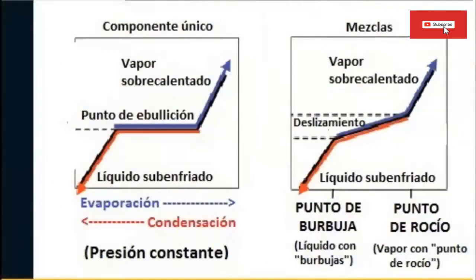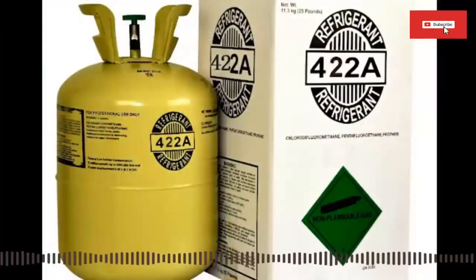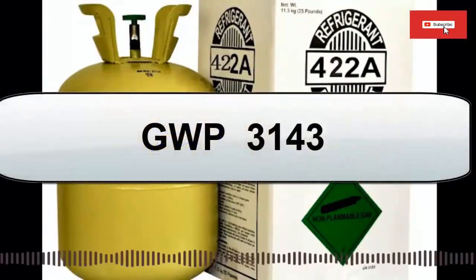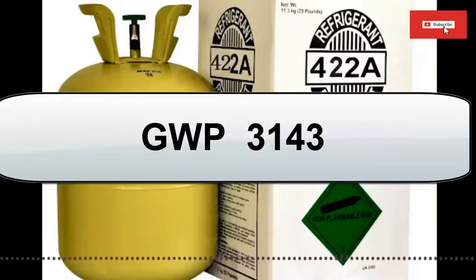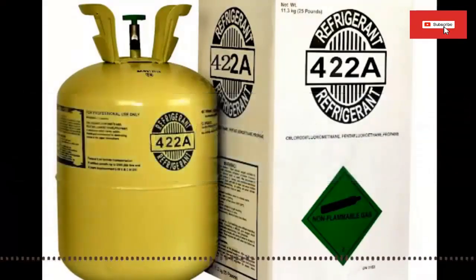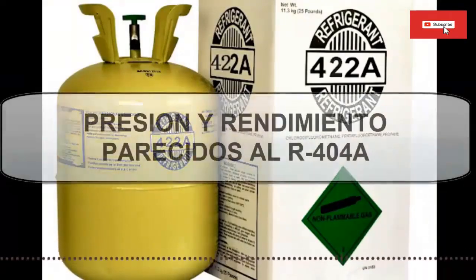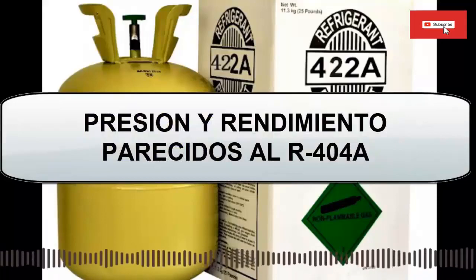4. R422A refrigerant has a slip of approximately 12. 5. R422A refrigerant has a GWP, global warming potential, of 3,143. This can actually affect the use of this refrigerant when taking into account environmental restrictions for greenhouse gases. 6. The pressures and performances of the R422A refrigerant are very similar to those of R404A.